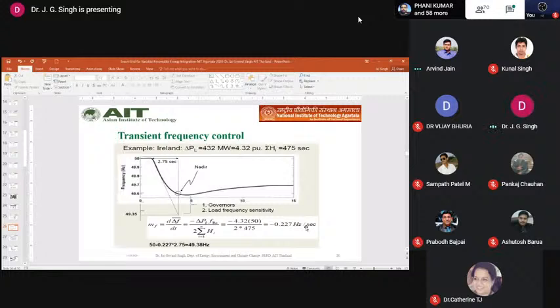And suppose inertia is divided by 4, four times lower than this. So just put 1 by 4 here, you get multiplied by 4, and it will be something like 0.9 hertz per second. It means if you reduce the inertia by 4 times, the rate of change of frequency drop will be 4 times, say around 1 hertz per second, and no power plants will start in 1 second except online battery storage. So even the fastest, like a diesel generator, takes like a minute or so.